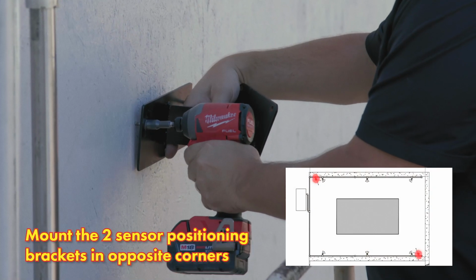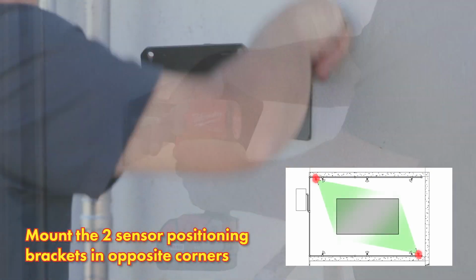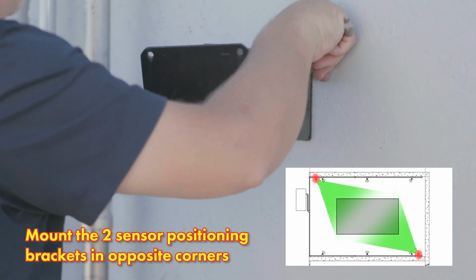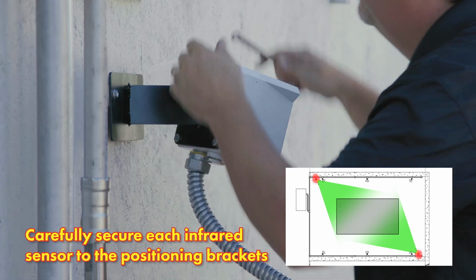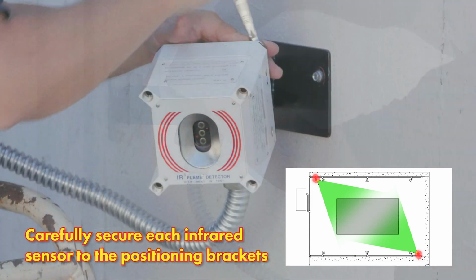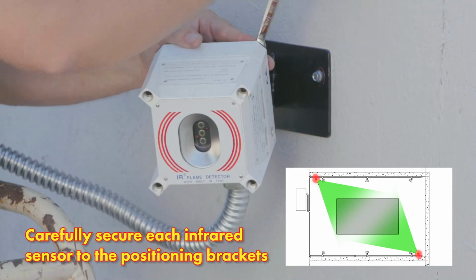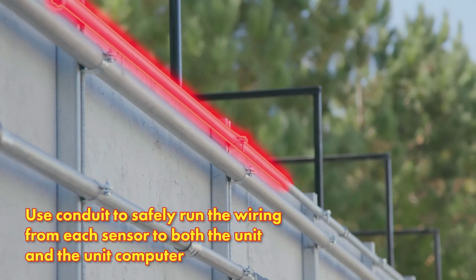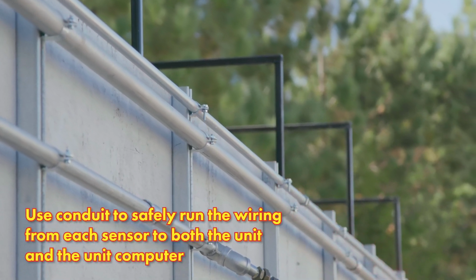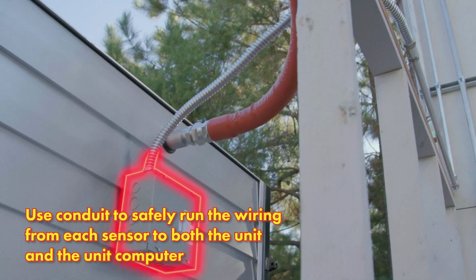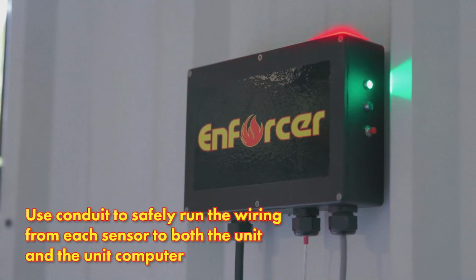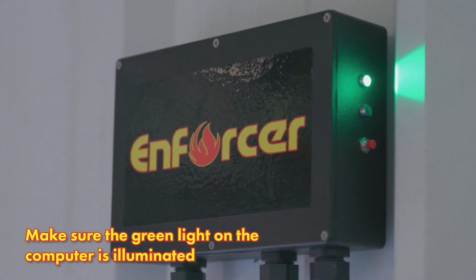Mount the two sensor positioning brackets in opposite corners to ensure all sides of the transformer are visible to the sensors. Carefully secure each infrared sensor to the positioning brackets. Use conduit to safely run the wiring from each sensor above your piping into both the unit and to the unit computer. Once all wiring connections are made and the computer and power supply are mounted, make sure the green light on the computer is illuminated.